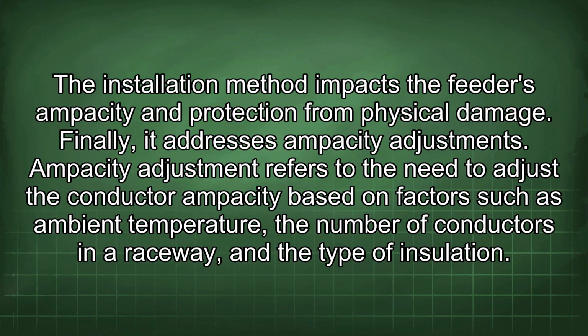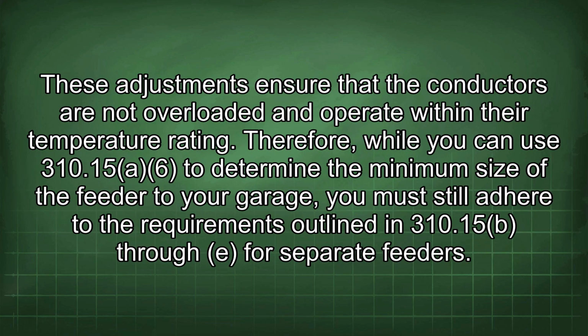Finally, it addresses ampacity adjustments. Ampacity adjustment refers to the need to adjust the conductor ampacity based on factors such as ambient temperature, the number of conductors in a raceway, and the type of insulation. These adjustments ensure that the conductors are not overloaded and operate within their temperature rating.